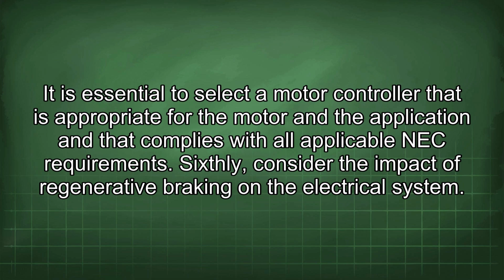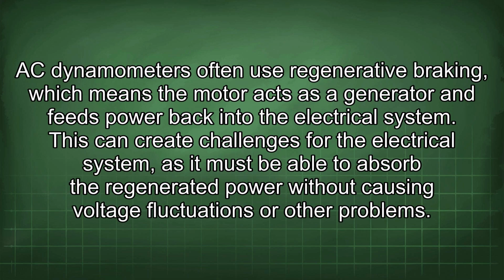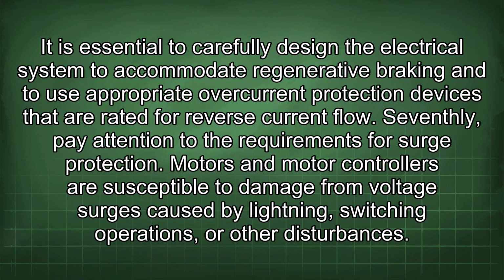Sixthly, consider the impact of regenerative braking on the electrical system. AC dynamometers often use regenerative braking, which means the motor acts as a generator and feeds power back into the electrical system. This can create challenges for the electrical system, as it must be able to absorb the regenerated power without causing voltage fluctuations or other problems. It is essential to carefully design the electrical system to accommodate regenerative braking and to use appropriate overcurrent protection devices that are rated for reverse current flow.